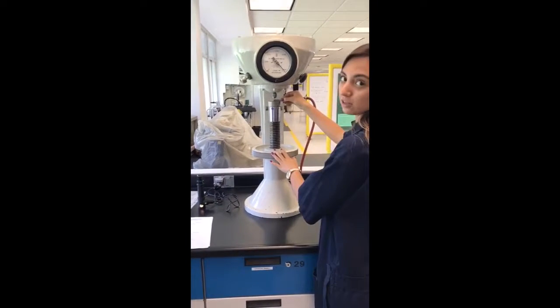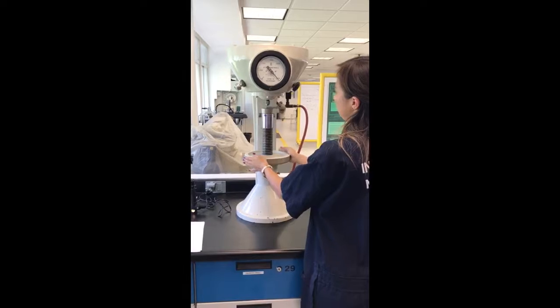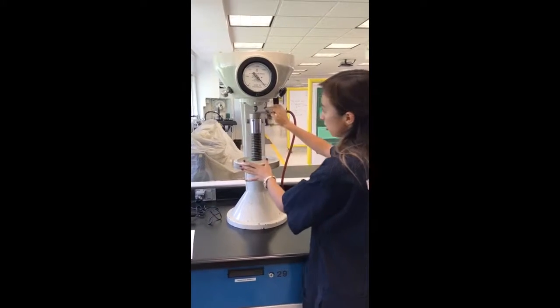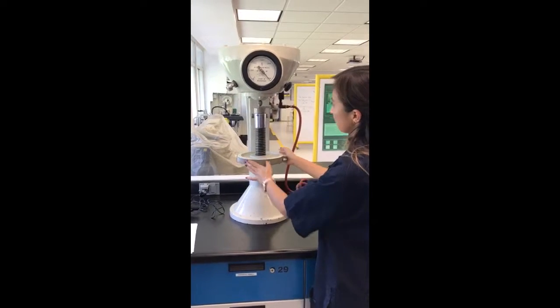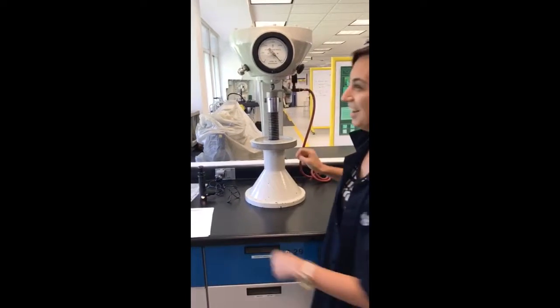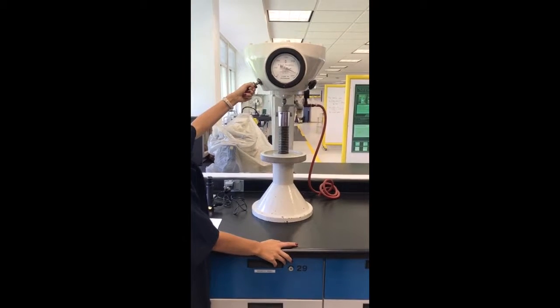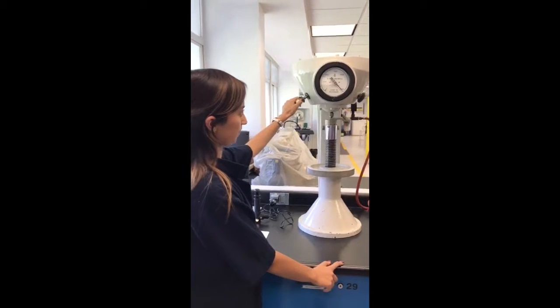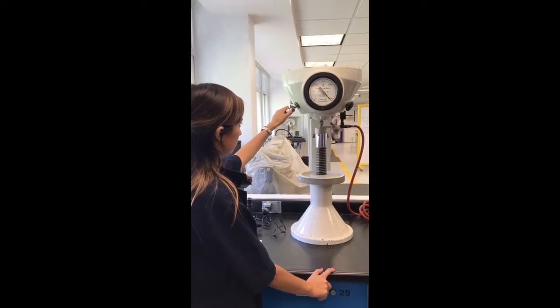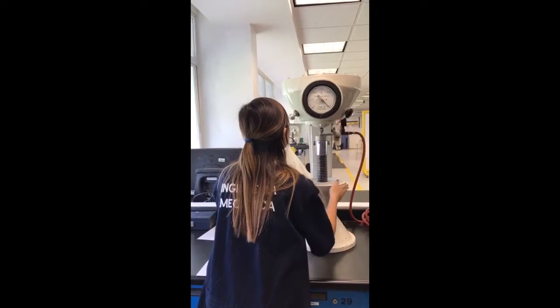First, we did the probe in the Brinell machine. We're gonna put the sample in the machine at the middle, and then we're gonna close it till it touches. And then we're gonna put the pressure, then we're gonna pull this. And we're gonna wait 15 seconds. And after we take the sample, we put it into a little microscope where we checked the diameter of the hole, and by this way we took the hardness of Brinell at the end of the practice.